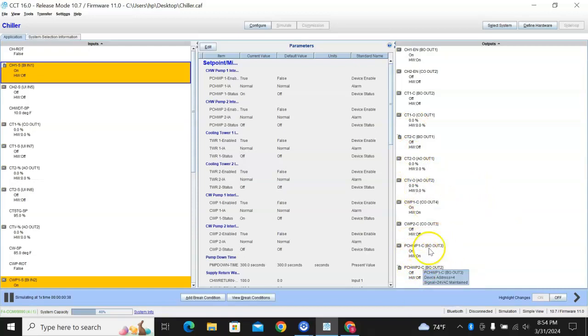So we do have a primary pump on. We do have a condenser water pump on. So right here is our bypass CTV. And 0% is 100% bypass. So right now we're bypassing the tower. Nothing's going over the top of the tower. And CTs are our towers. So we're right at set point.